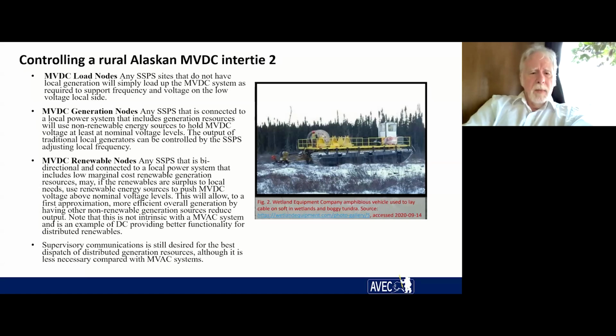At the bottom, supervisor—I'm not saying you don't need supervisor communications. With a multiplicity of generation sources, you want to run the lowest marginal cost generation source at all times, and that does require some supervisory communications. However, at least it's being overlaid on a system that's intrinsically stable.